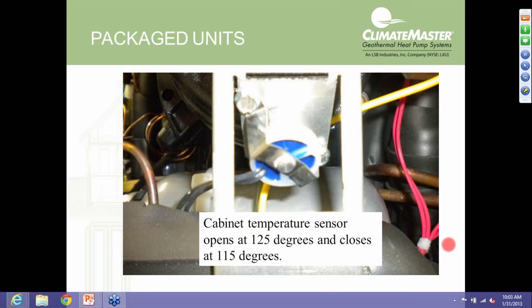potentially slow down the pump, depending on where the pump is running. It'll essentially go to pretty close to 75% pump speed, and that is to protect the pump at those higher ambient temperatures. Now, that being said, in some applications that may not be a problem. You may not even be running at that type of speed. But where this really applies is mainly in the south, where we might be installing these units in an unconditioned space, and again, dealing with the higher temperatures that we see down south in the summer especially. We could be reaching those kind of temperatures in the cabinet.